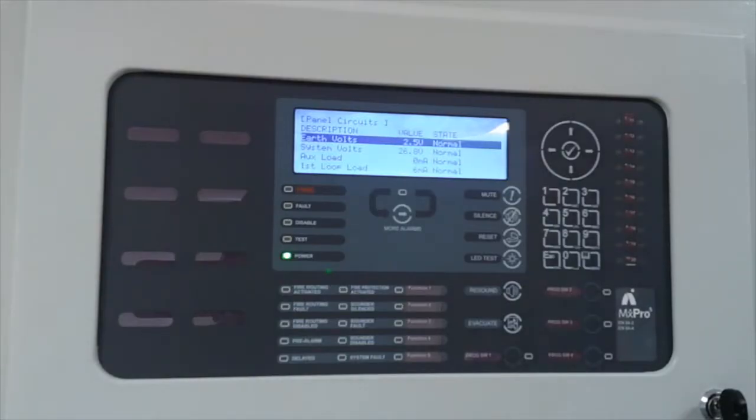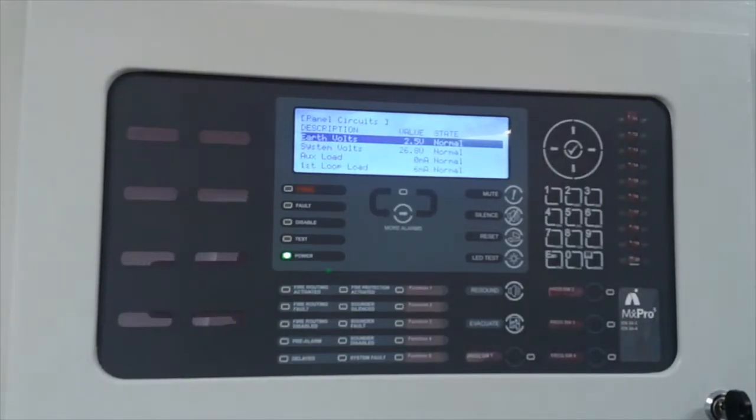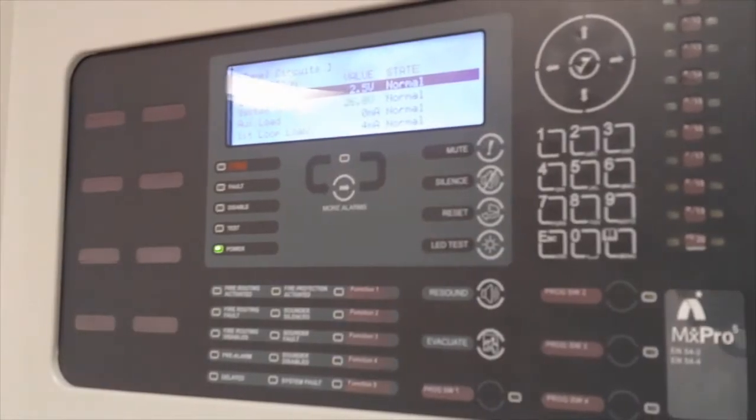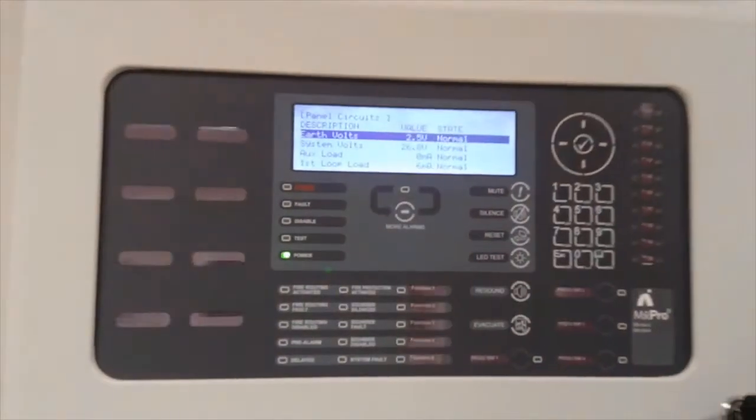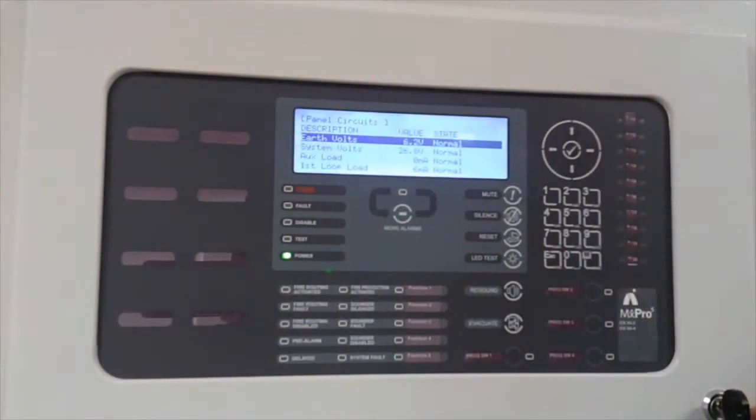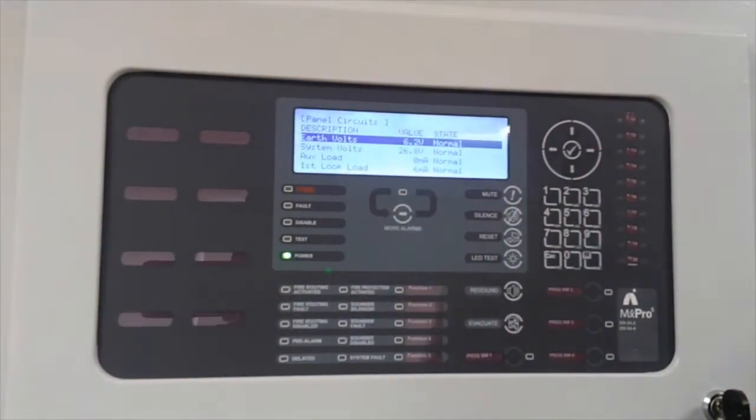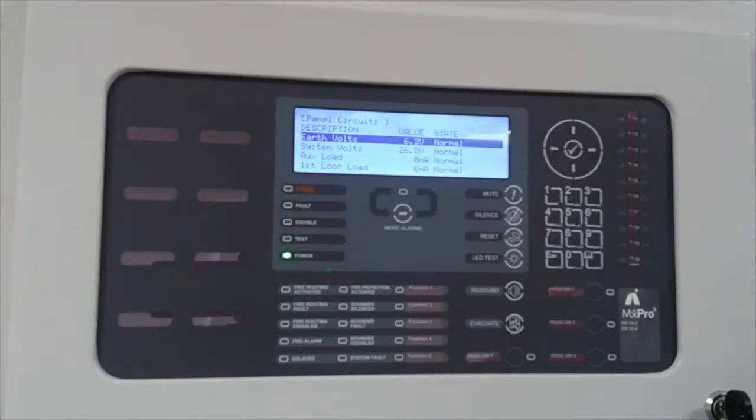So you can see by simulating a fault condition, I am going to cause a positive earth fault. So generating an earth fault, you can see that voltage is rising. That will now go into fault condition.